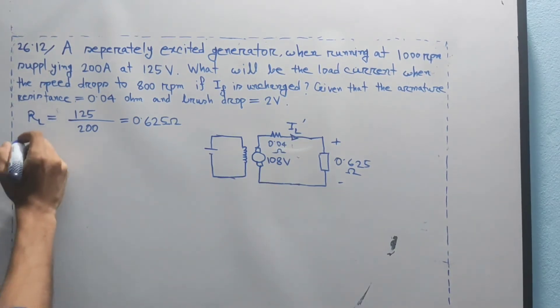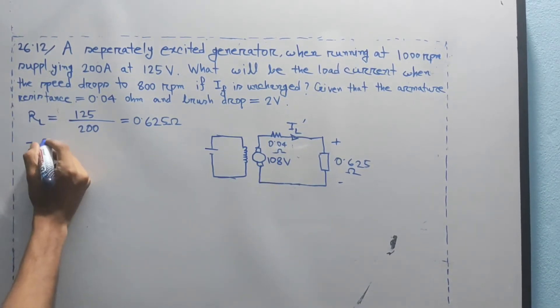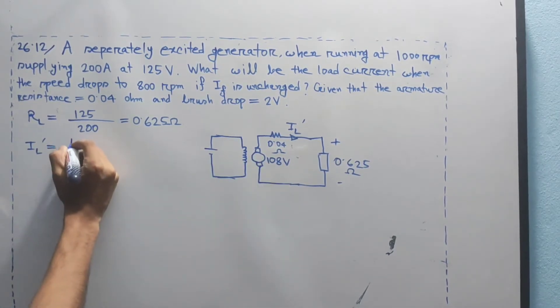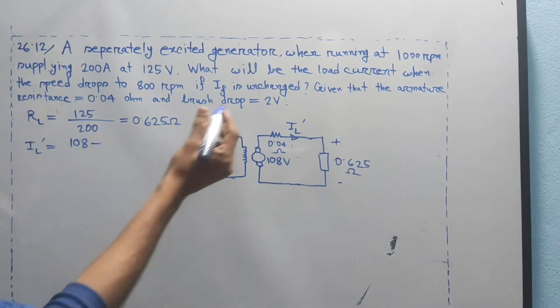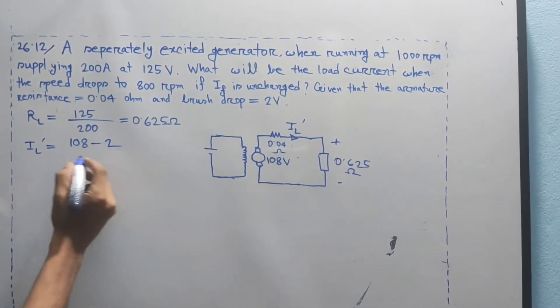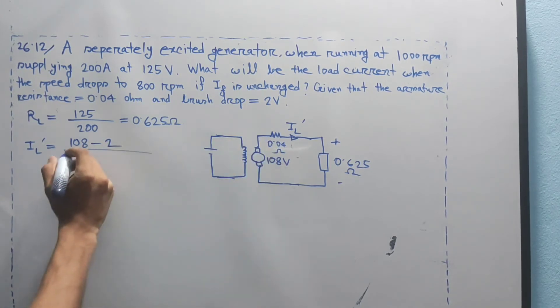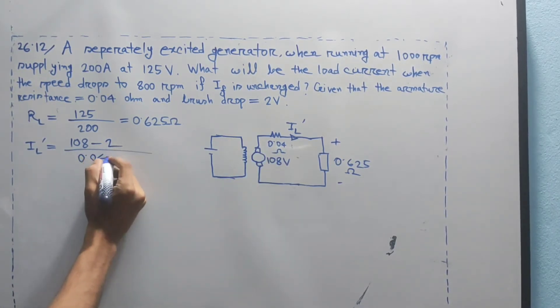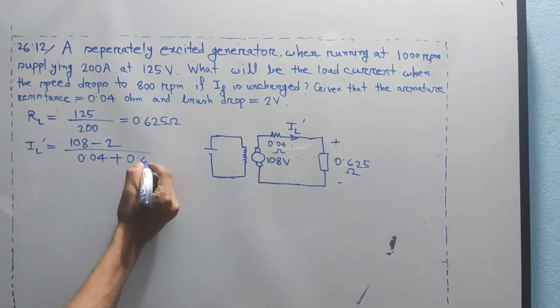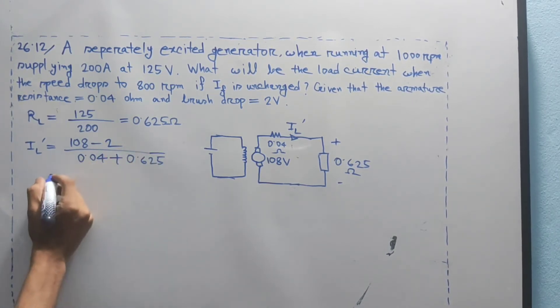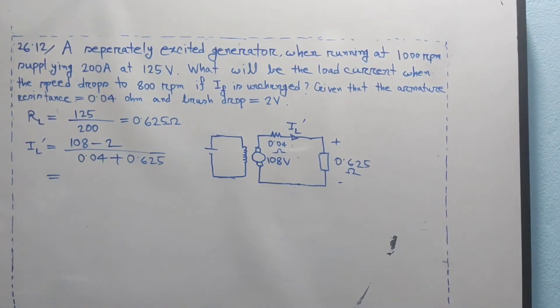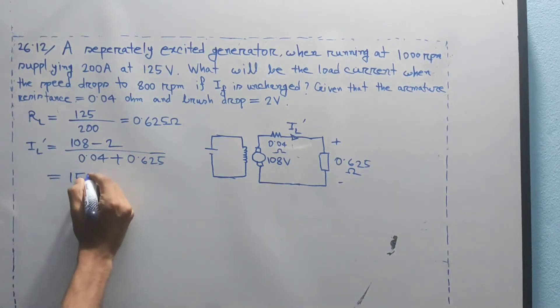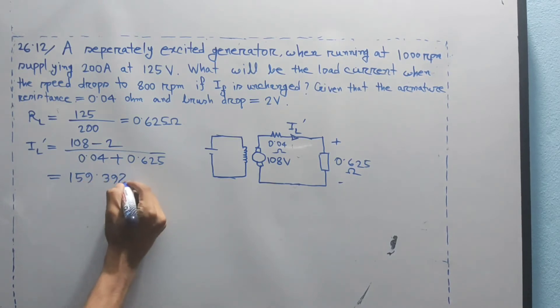Now we find the new load current IL prime. IL prime equals the new induced EMF minus brush drop, divided by total resistance: (108 − 2) divided by (0.04 plus 0.625). IL prime equals 106 divided by 0.665, which gives approximately 159.4 A.